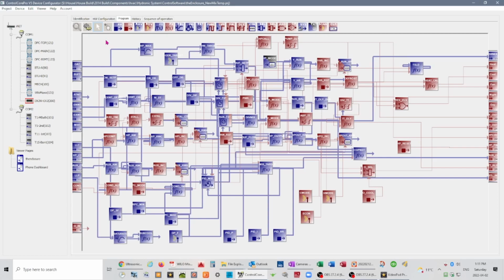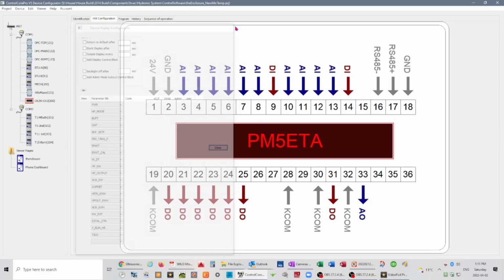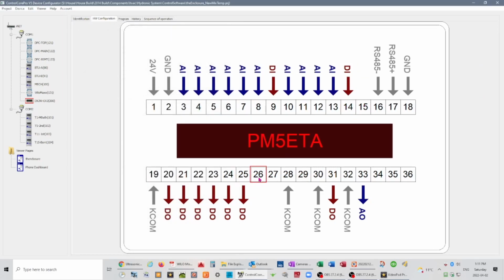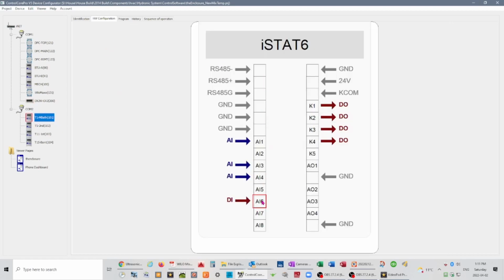Now, the input and output data types differ depending on what type of device it was. I showed you here that we only had digital output, and here we only had analog input and digital input. But if, for instance, we go to one of the iStats, we can see we've got analog input, digital input, counter, frequency, and then off. That allows for a lot more flexibility in what you're connecting as far as sensors and the like. And on output, we have analog output or digital output. The analogs can be converted to digital. So again, it's based on the device itself. We'll have unique available data types that it's been programmed to accept and to act upon.